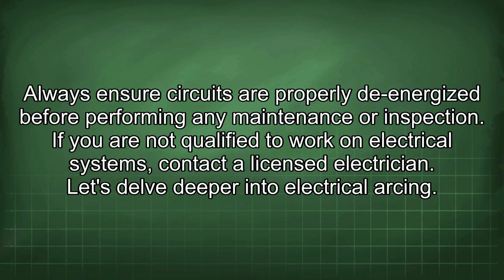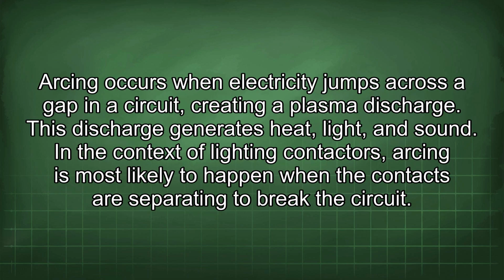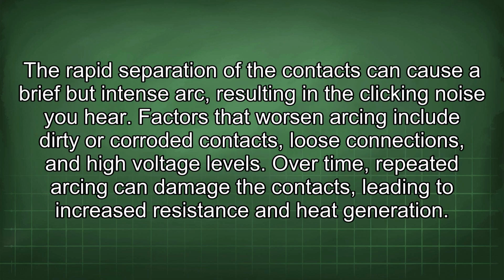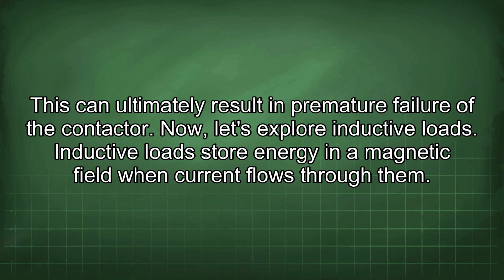Let's delve deeper into electrical arcing. Arcing occurs when electricity jumps across a gap in a circuit, creating a plasma discharge. This discharge generates heat, light, and sound. In the context of lighting contactors, arcing is most likely to happen when the contacts are separating to break the circuit. The rapid separation of the contacts can cause a brief but intense arc, resulting in the clicking noise you hear. Factors that worsen arcing include dirty or corroded contacts, loose connections, and high voltage levels. Over time, repeated arcing can damage the contacts, leading to increased resistance and heat generation. This can ultimately result in premature failure of the contactor.